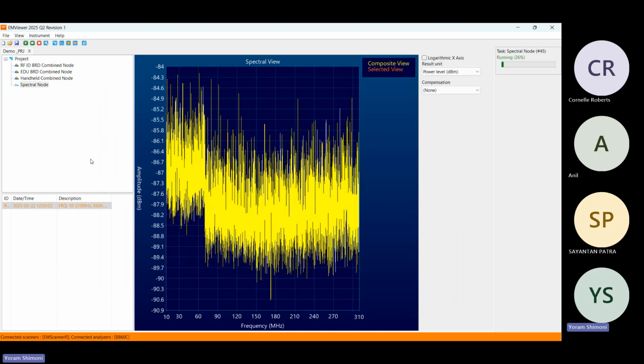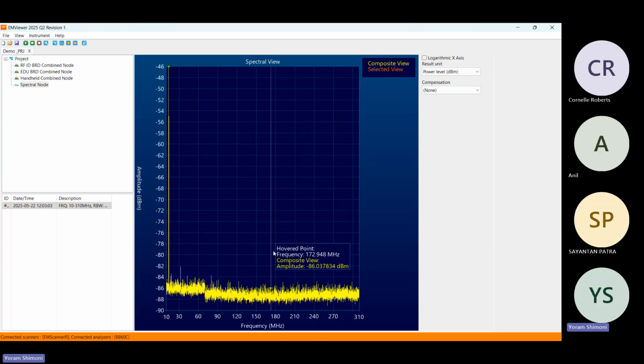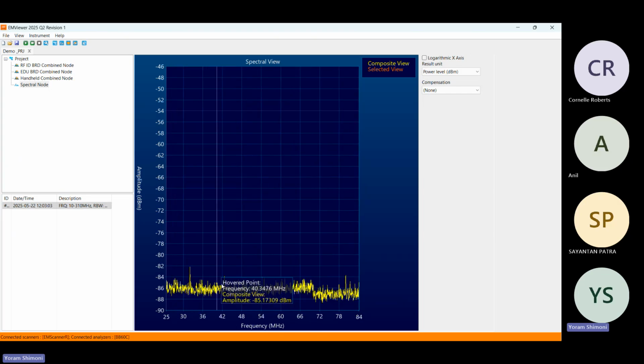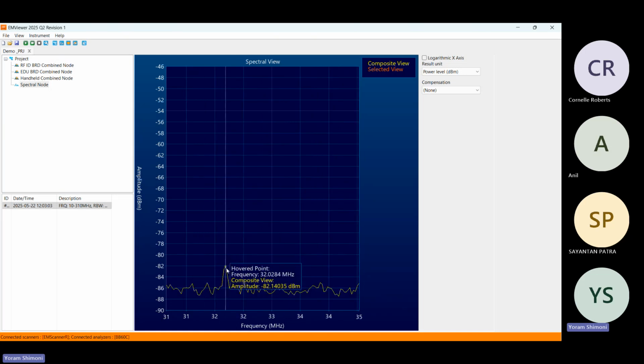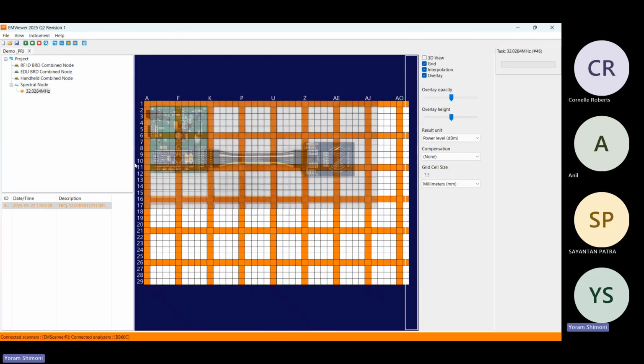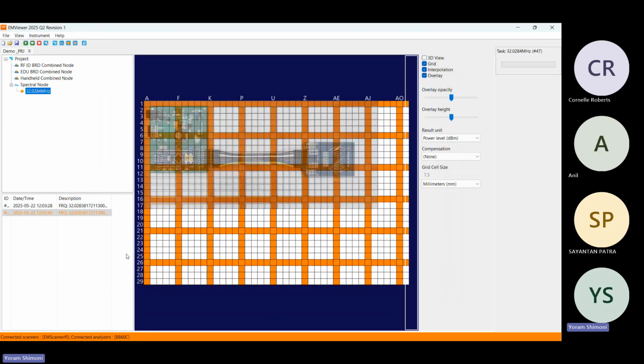This is kind of a spectral scan only, just to identify the frequencies that are present. Now you can select a certain frequency, like you can see the peak here, or for example this one, the 32. I can select it and run a spatial scan at the selected frequency. So this one is a scan of only that frequency. So it's a single frequency scan.